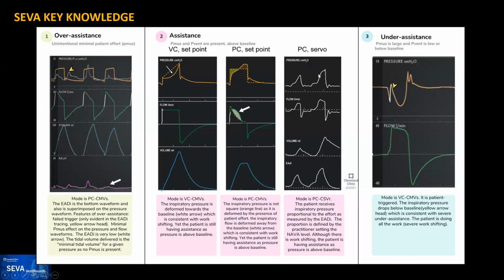And the last one is the servo, in which you can see that as the patient does more effort, this is the electrical activity of the diaphragm, the pressure delivered is higher the more there is. And so this is assistance. Depending on the clinical situation, it may be appropriate or not, but the fact is that the ventilator is assisting the patient. Then we have under assistance, which is what we would call severe work shifting.